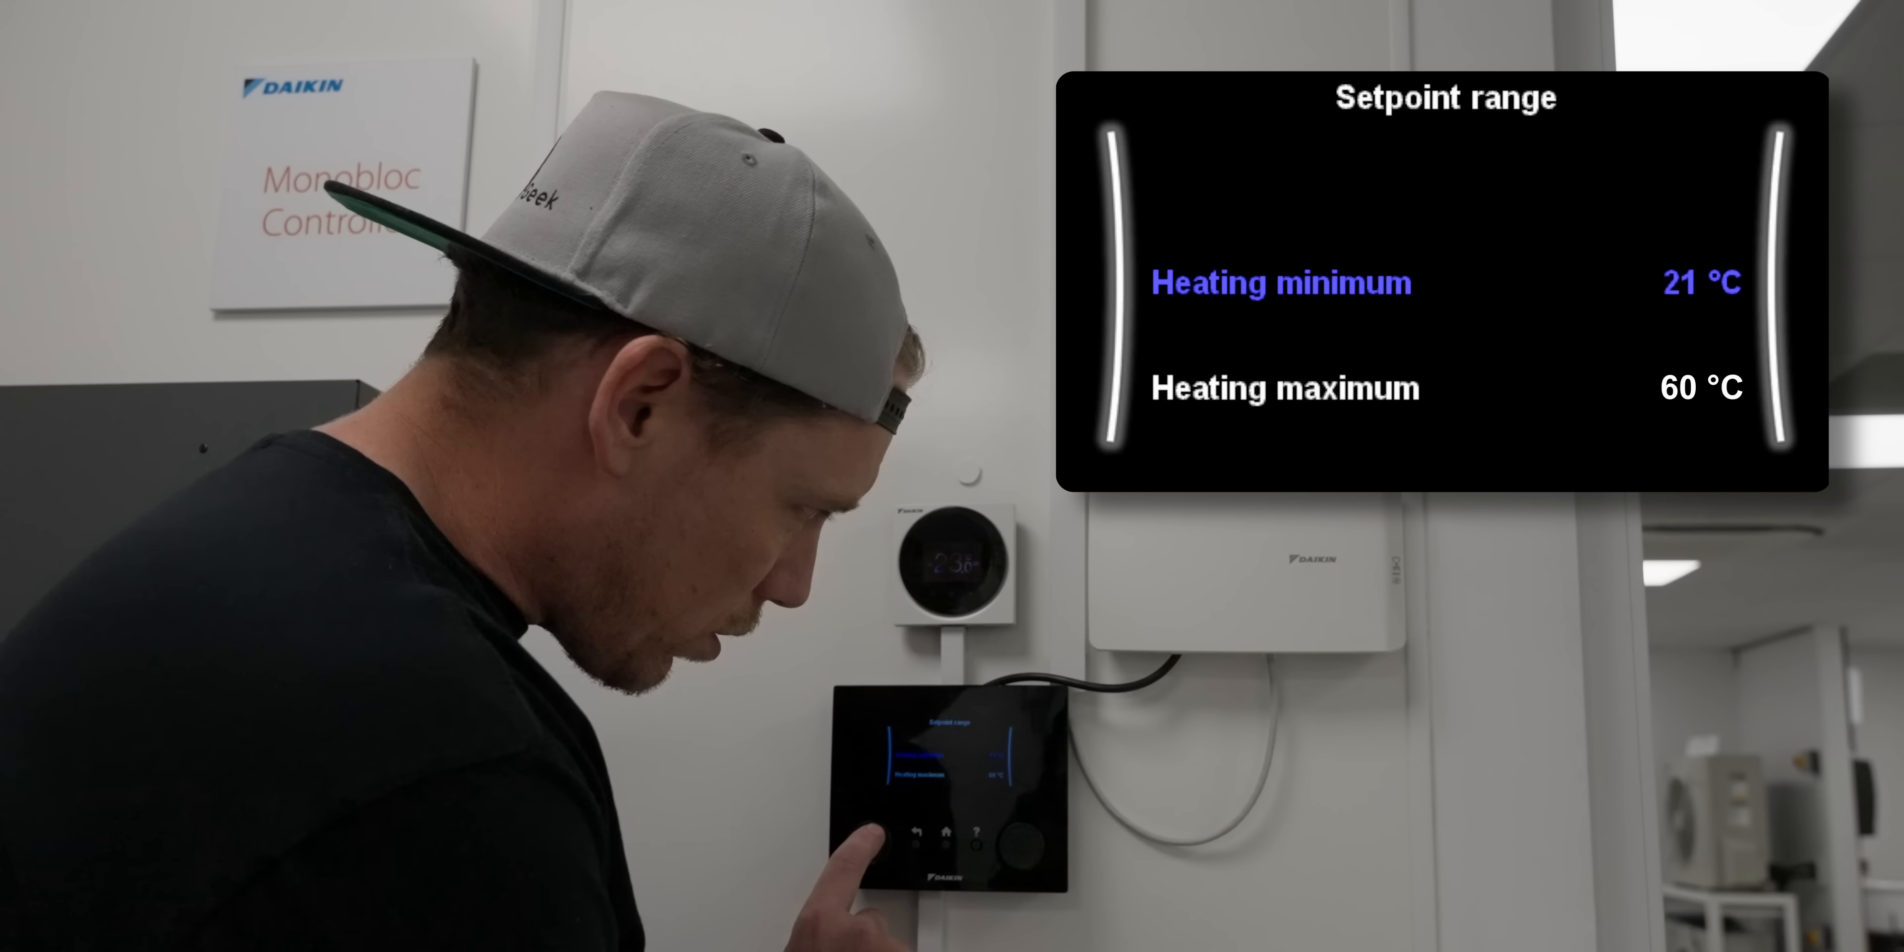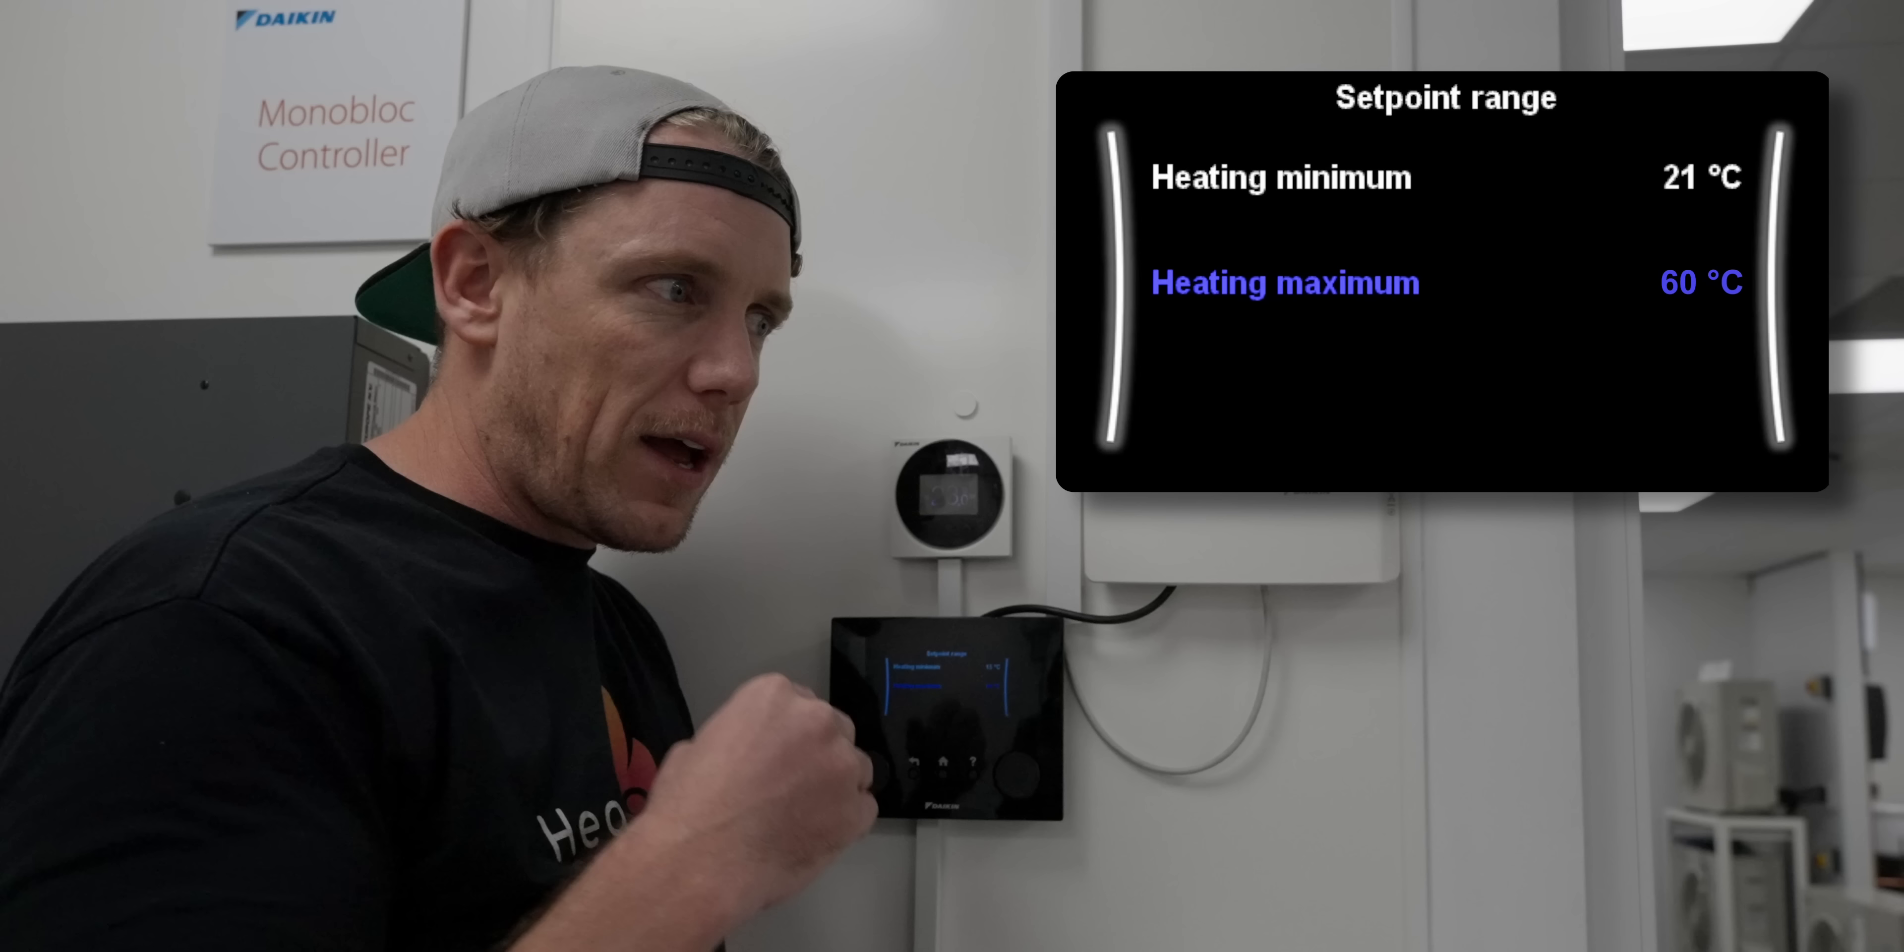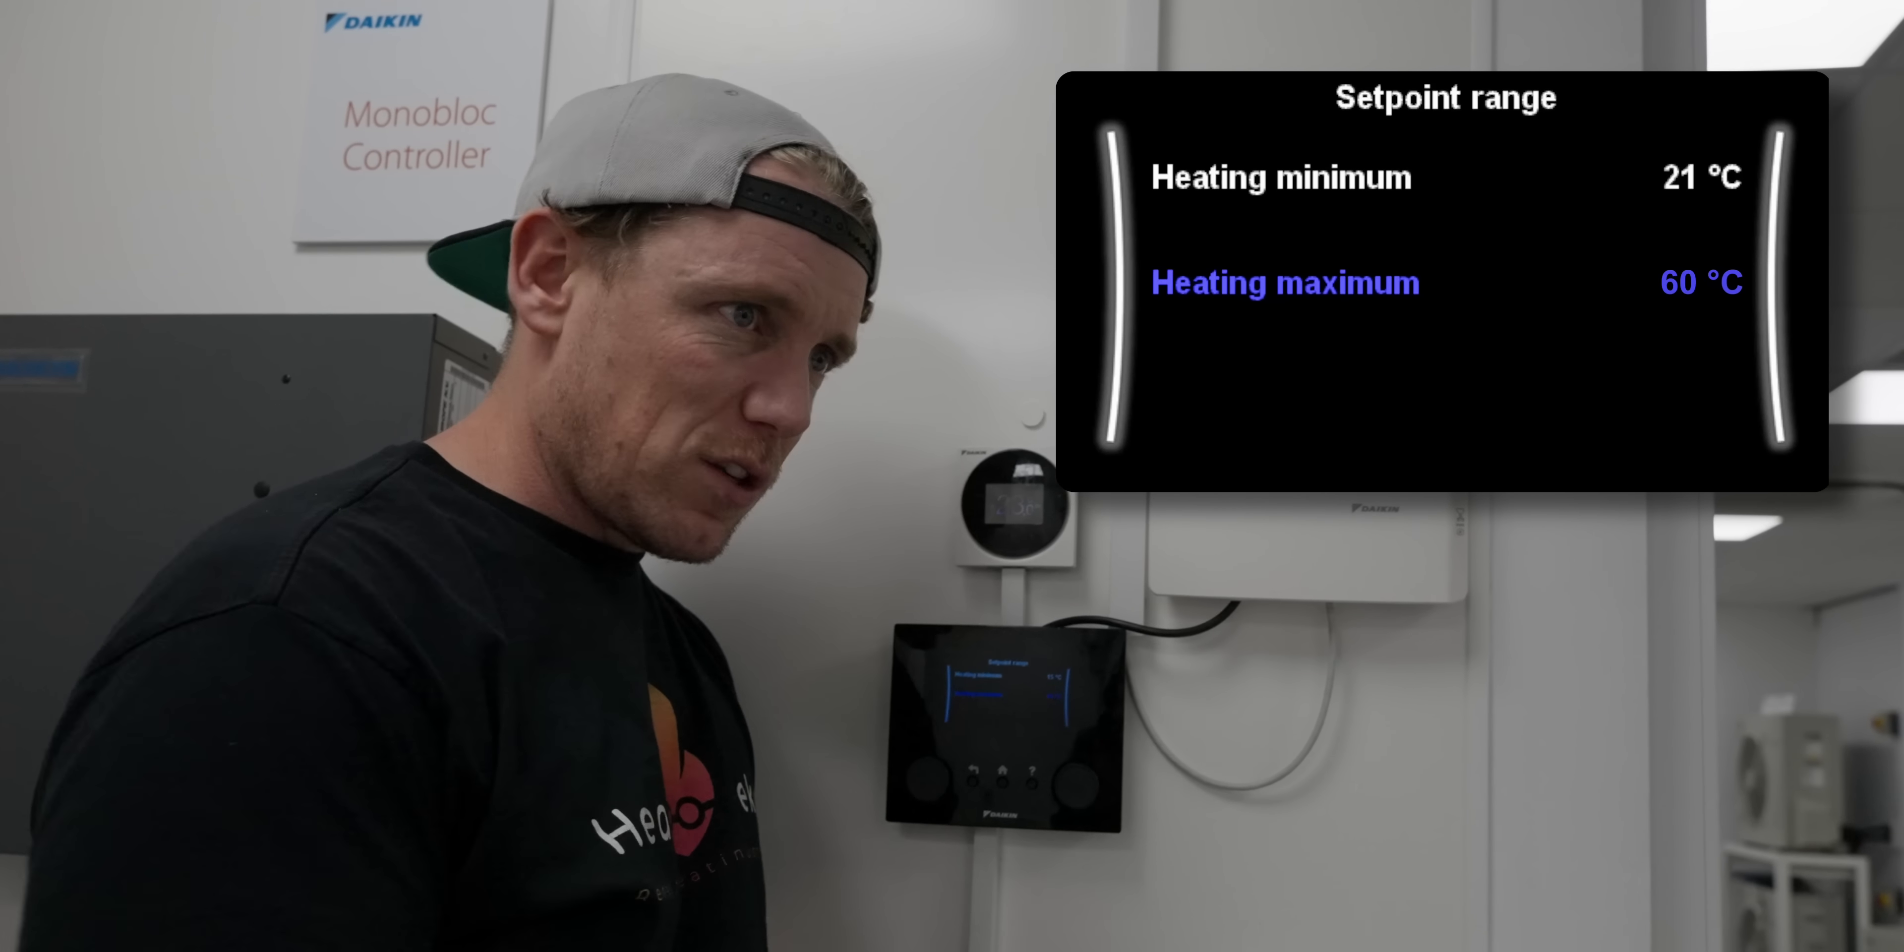Next, set point range. This is heating minimum, minimum flow temperature, maximum flow temperature. We don't need 60, so if we brought it back down from 60 that may help. But if your heat pump's oversized anyway, the cycles will be shorter. You can set it to whatever you wish, it doesn't matter because you've already set weather compensation, it's not going to see it anyway.